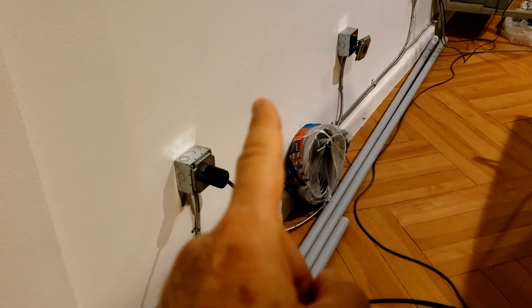Now, the problem with that is, the manufacturer recommends 6 gauge wire between the box and the disconnect that's going to be outside. There will be a disconnect so you can shut the circuit off there, and then 8-gauge wire from the disconnect to the compressor that'll be outside, the other side of this wall. So this 10-gauge wire that runs here and up through this PVC pipe and into the box is absolutely useless. It's got to come out.